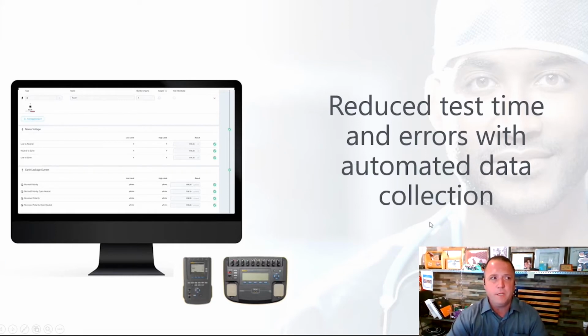What time can you get into an OR? Typically you can't start your service till they're done operating in your OR. So if you're one of those biomed shops with multiple technicians, you sometimes have a guy who starts at 3, 4 o'clock in the morning, or a technician who comes in at the end of the day, maybe 4 or 5 o'clock, and they don't even start their PMs until it's late. So they may have already worked part of a day. I was with a small ISO for 17 years, and a lot of times we would travel to the site and we'd have 4, 5, 6 hours before we could even start.